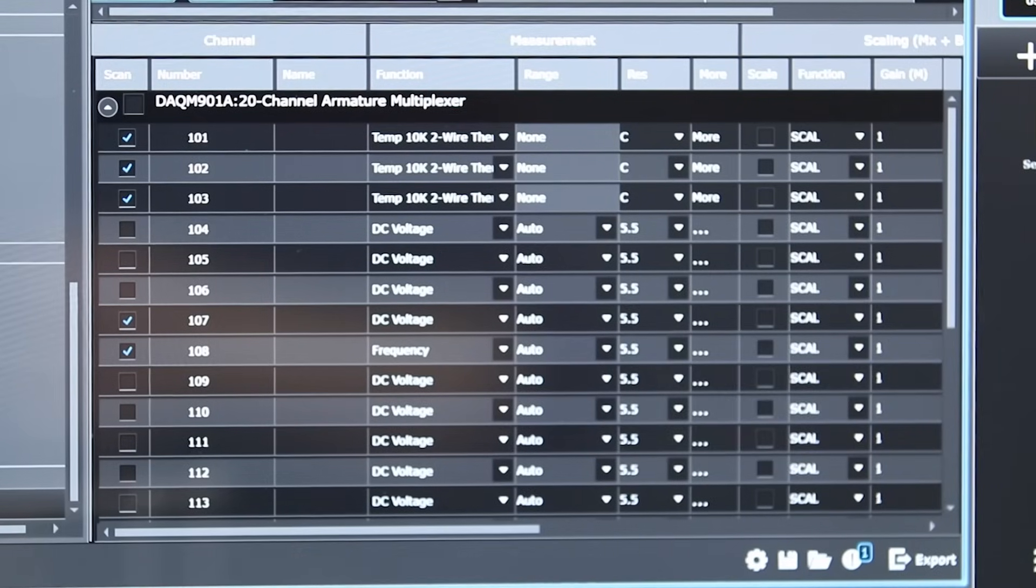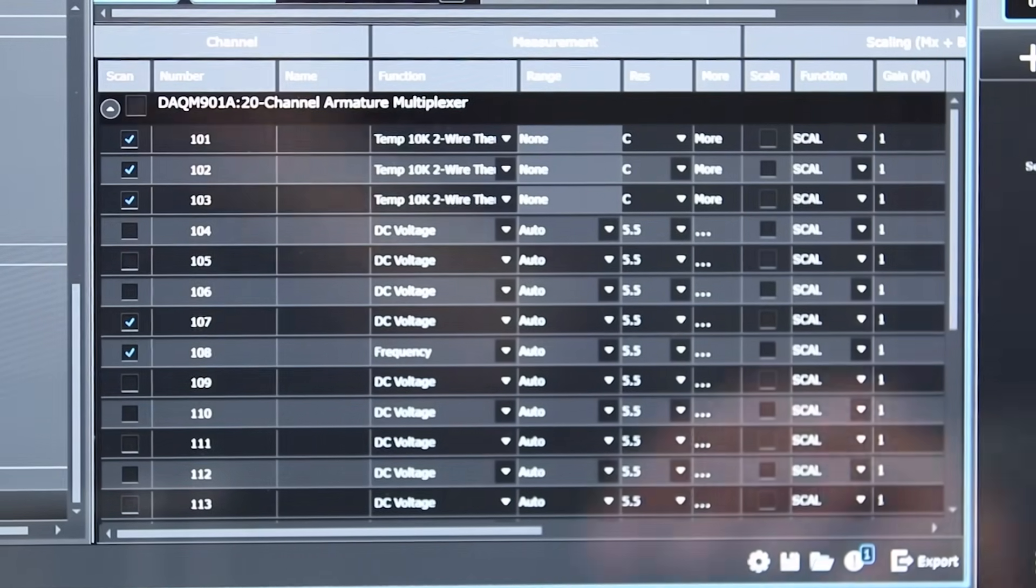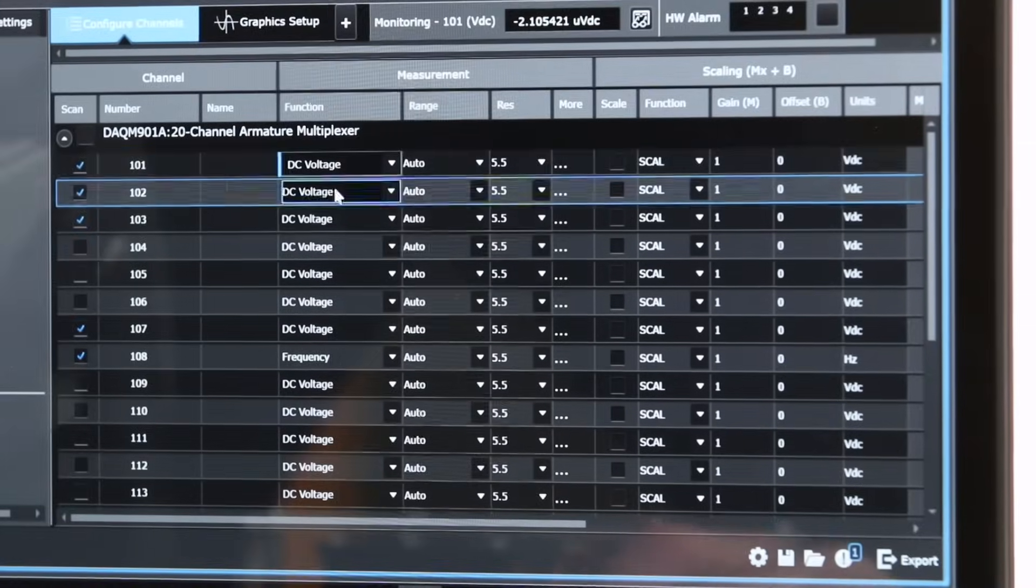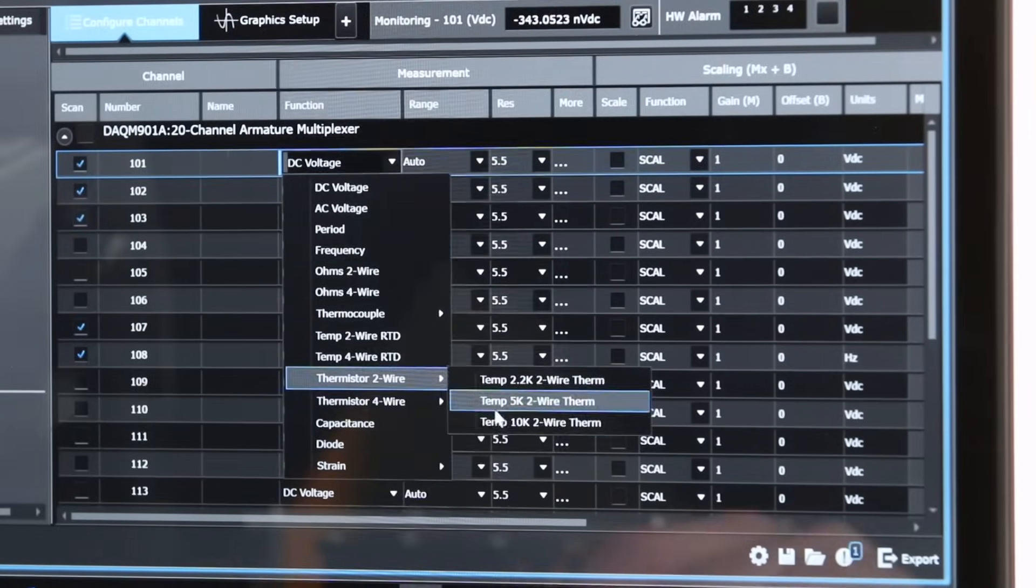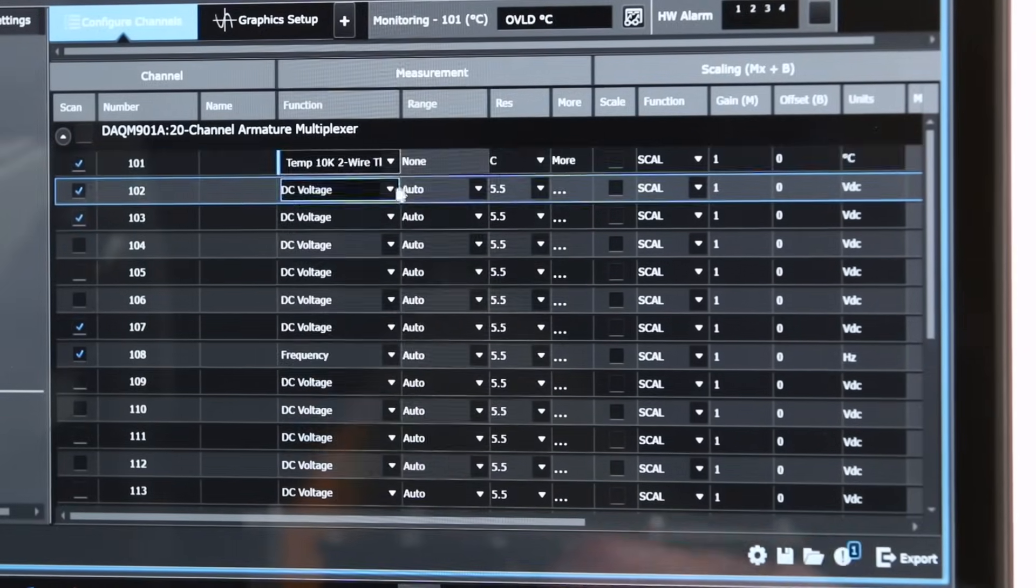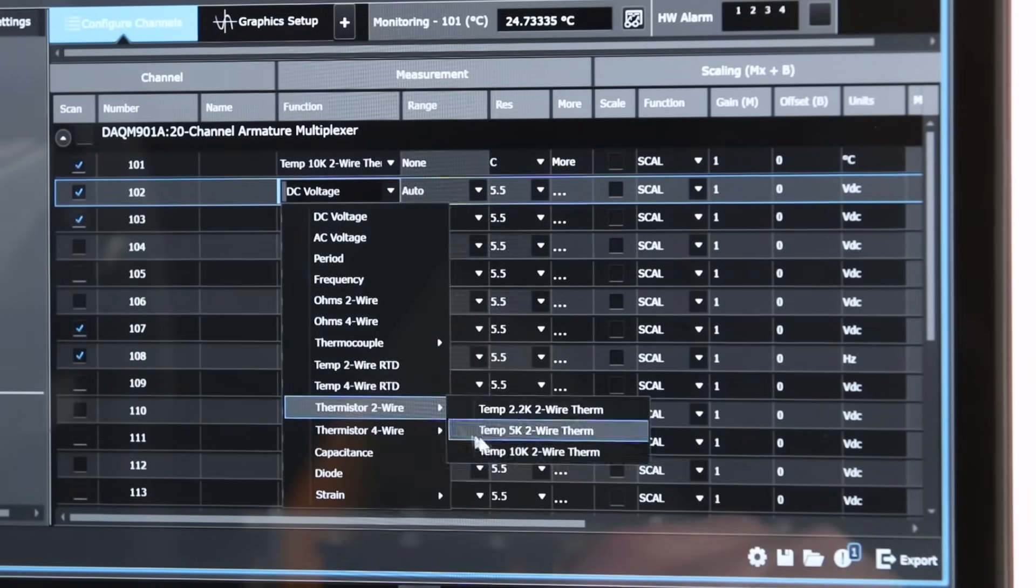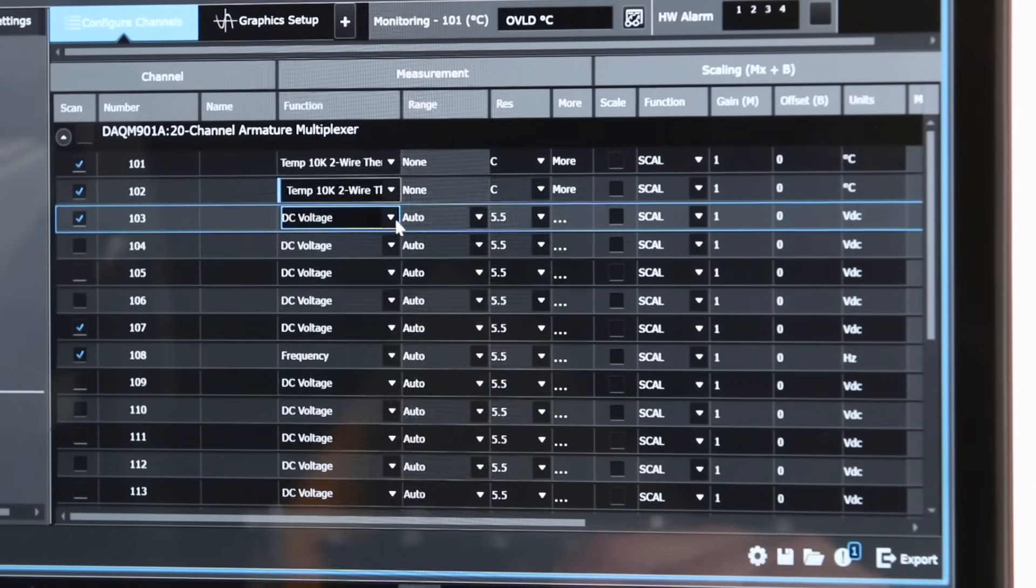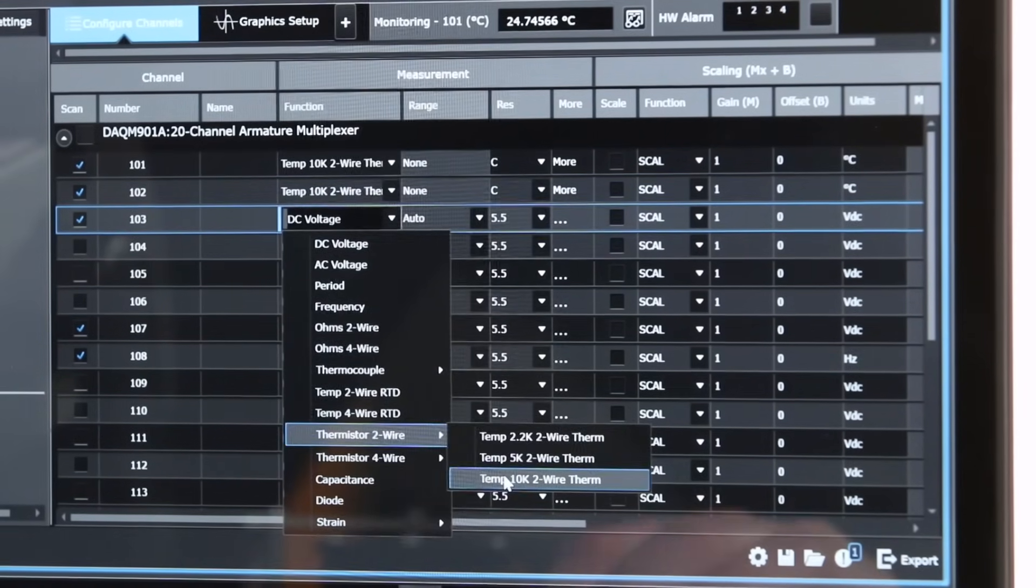The configuration panel allows you to see all the channel measurements in one view. Configuration for each channel is as easy as point and click when selecting measurement functions, range, resolution, scaling, and if needed, access to advanced controls such as gain, offset, and alarm settings.